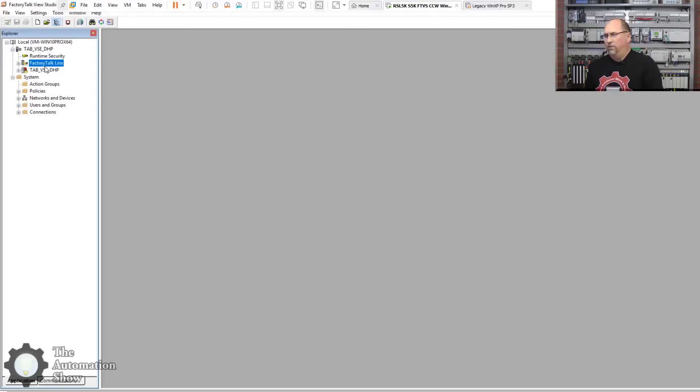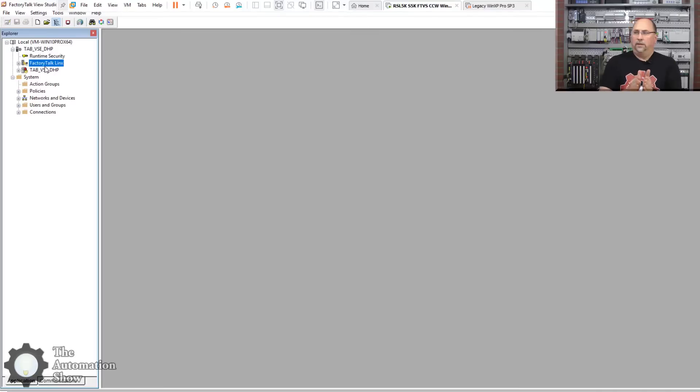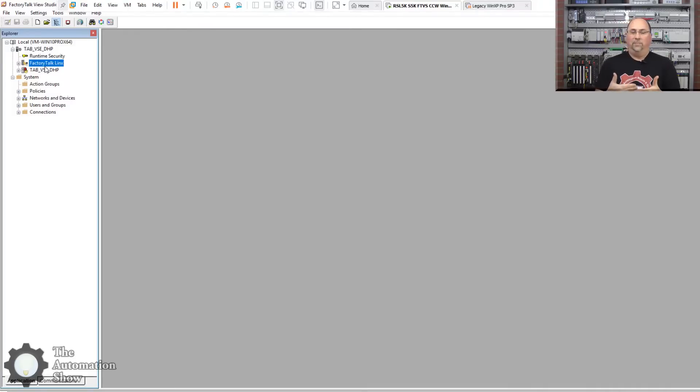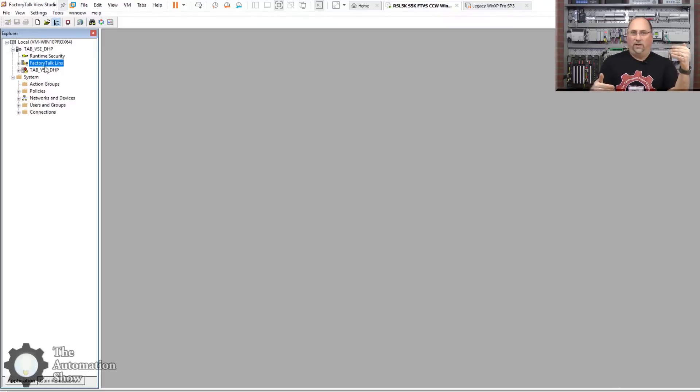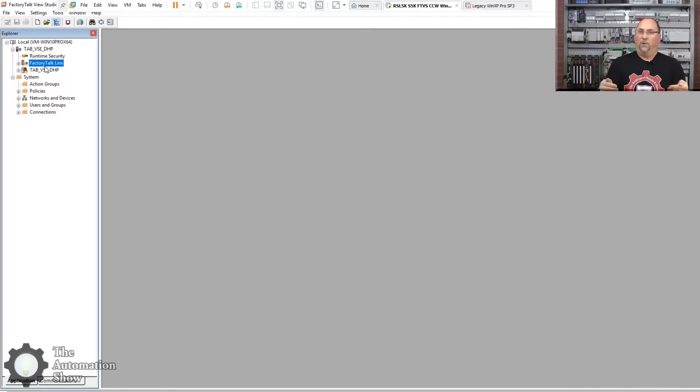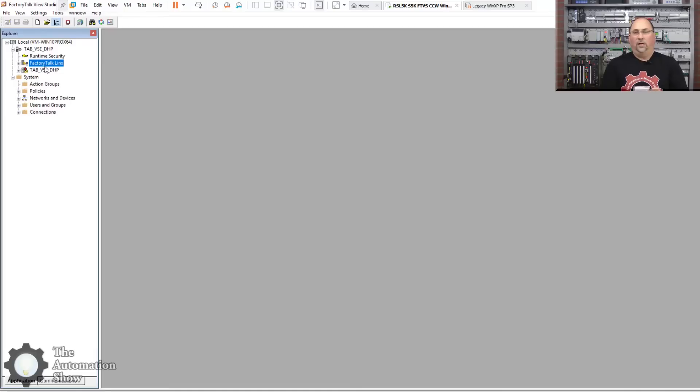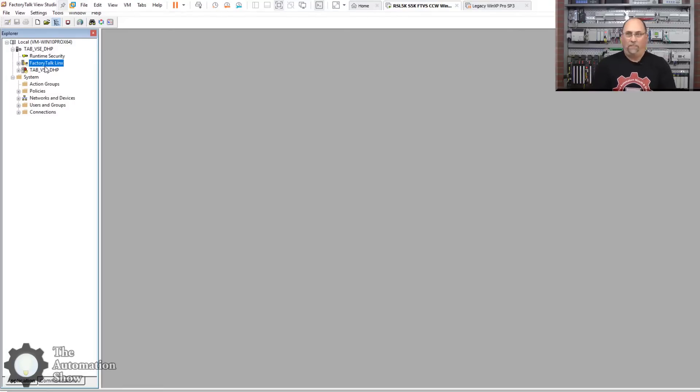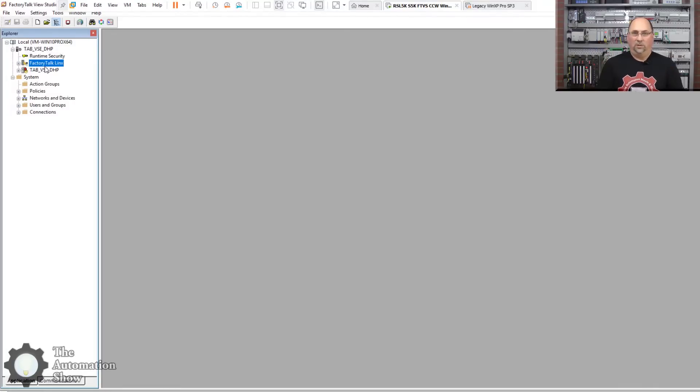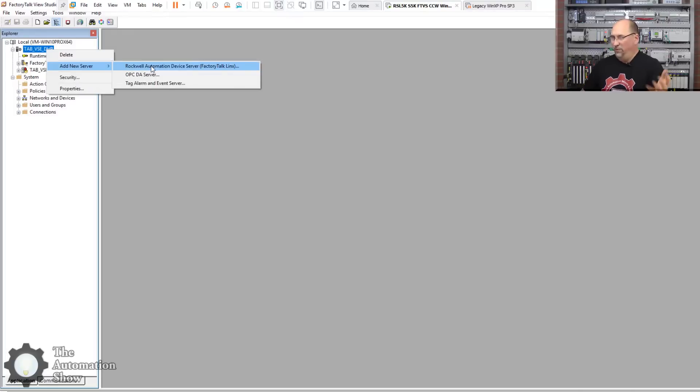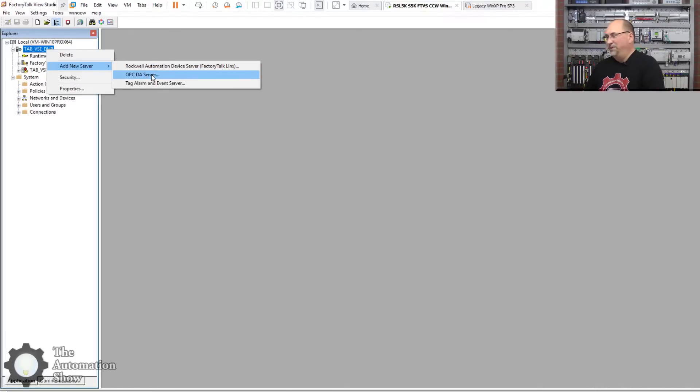Now you don't want to have RS Links Enterprise, Factory Talk Links, in your project and RS Links Classic in your project if they have similar or they have the exact same names, like shortcuts versus topics. So if I had a PLC5 shortcut in RS Links Enterprise and a PLC5 topic in RS Links Classic, certain versions of the software get confused about that and it causes all kinds of issues. I'm not going to go into that in great detail, but trust me, if you do have RS Links Classic and RS Links Enterprise in the same Factory Talk View project, make sure all your shortcuts and topic names are unique. Otherwise it gets ugly and I've run into some people that have to do a lot of rework to their project because of that. So in any case, I don't want to go into the details on that, but if you're interested let me know and I will.